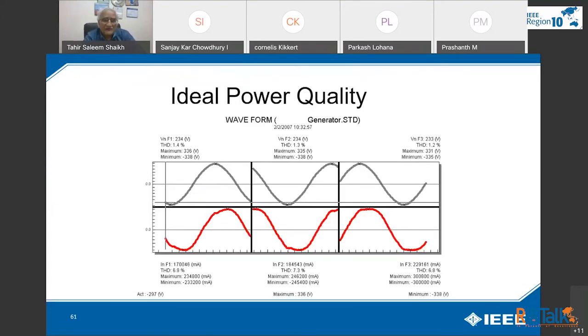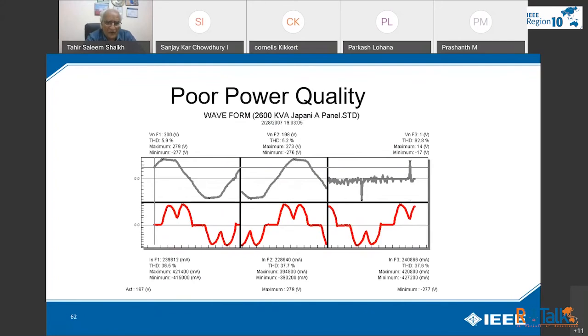If you come to an ideal power quality, this is a picture taken by our spectrometer that shows the power quality. The above is the voltage and the lower is the line of current, and THD level varies 1.4, 1.3 and 1.2, and 6.9, 7.3 and THD 6.8. So this is ideal, and this is a defective drive operating. And you can see over here, the power is not much, but the current harmonics is 36.5, 37.7. And the third phase, there is some problem in connection. So I will not discuss 37.7, but it gives you 37.6.